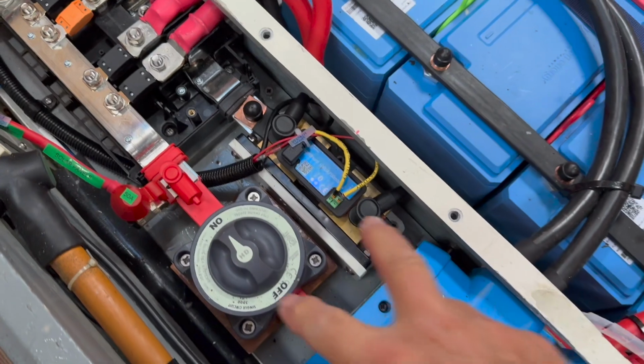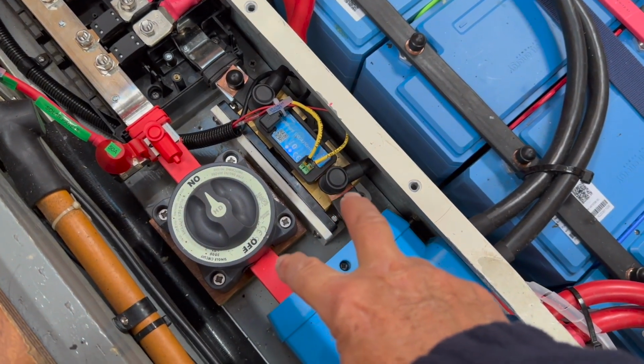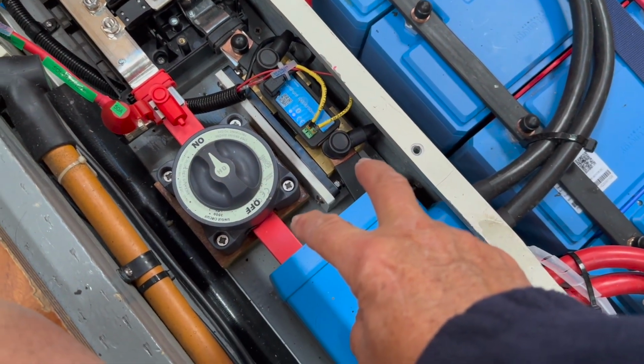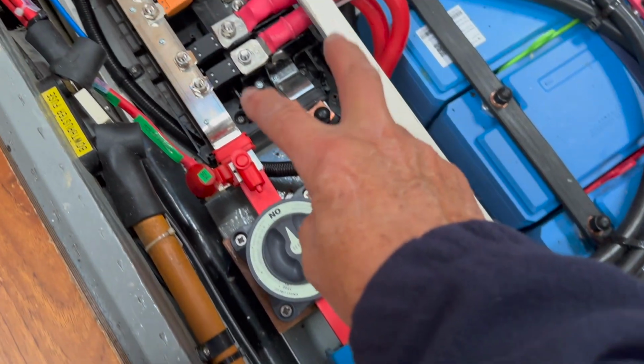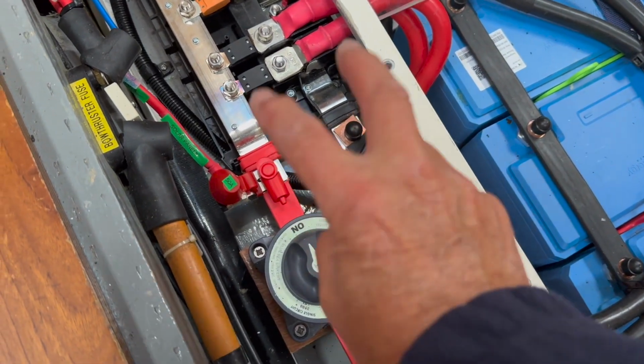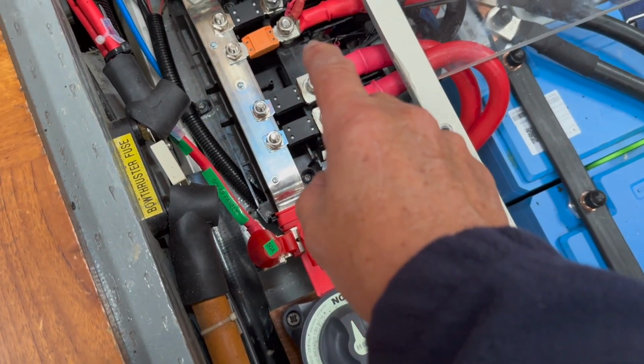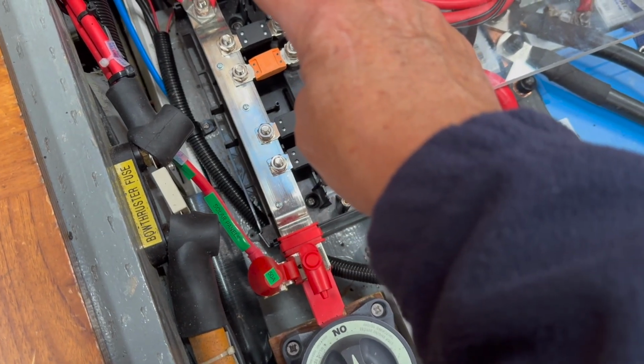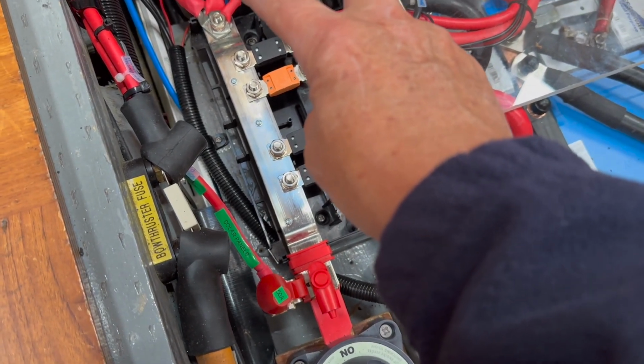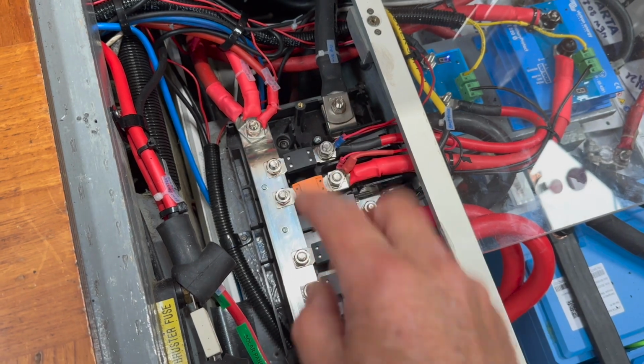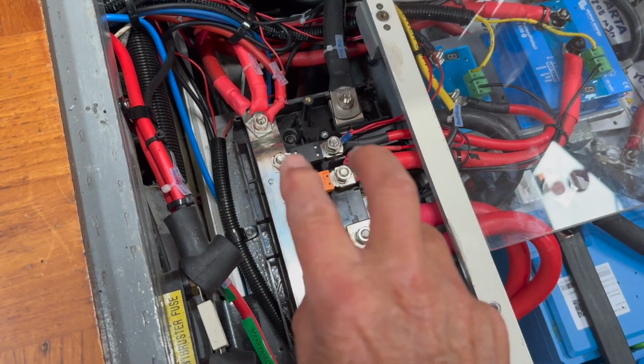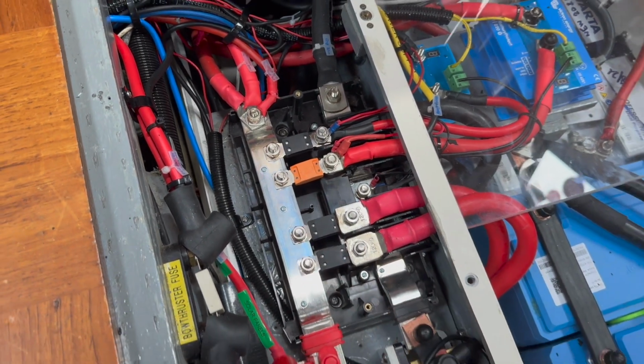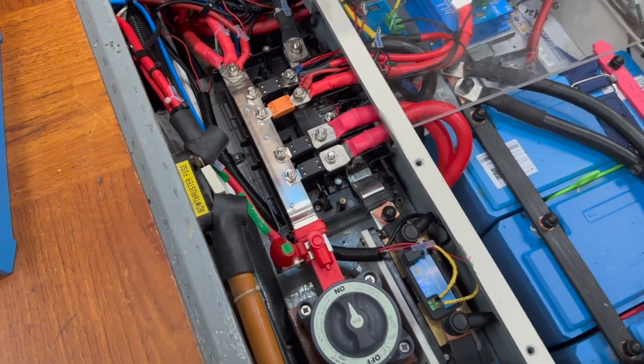I checked the voltages at the output from the battery system and they're all good. The other side of the shunts and switches is good. I'm getting power across the terminals at the back of the links units here, and I checked continuity across each of these fuses - they're all good.